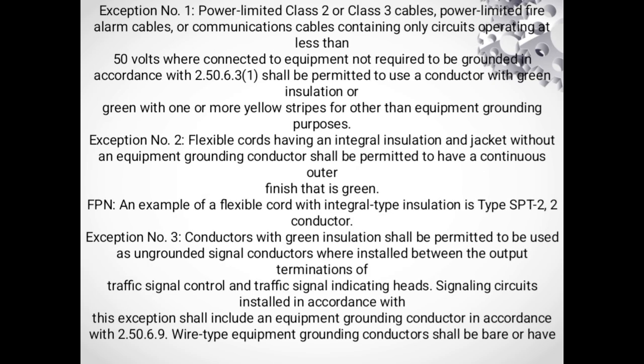Exception number 1, power limited Class 2 or Class 3 cables. Power limited fire alarm cable or communication cable containing only circuits operating at less than 50 volts, where connected to equipment not required to be grounded in accordance with 2.50.6.3, shall be permitted to use a conductor with green insulation, or green with one or more yellow stripes, for other than equipment grounding purposes.